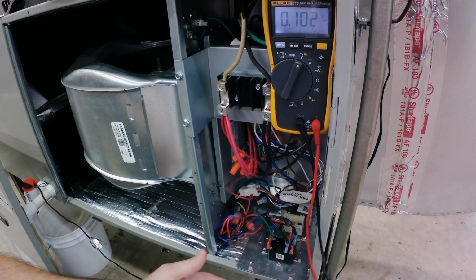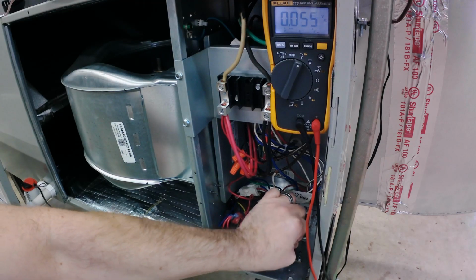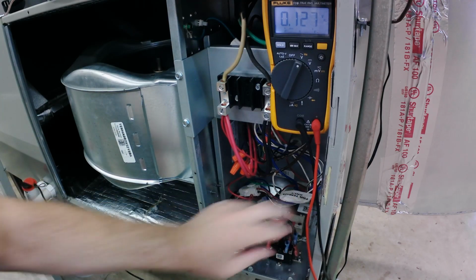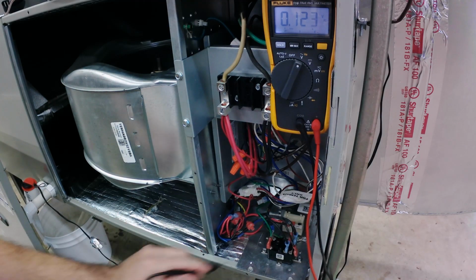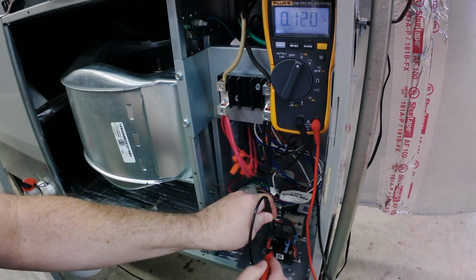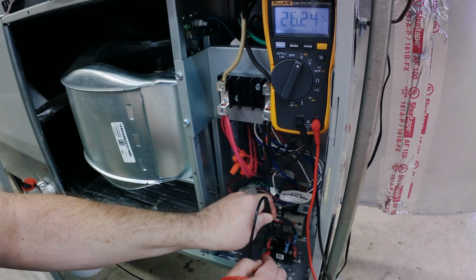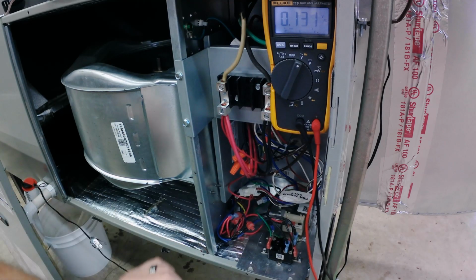Now, let's say that, and I'm going to take this off real quick. Let's say that I got 24 volts on the relay coil, but my fan still didn't work. The next step I would do is still low voltage related.